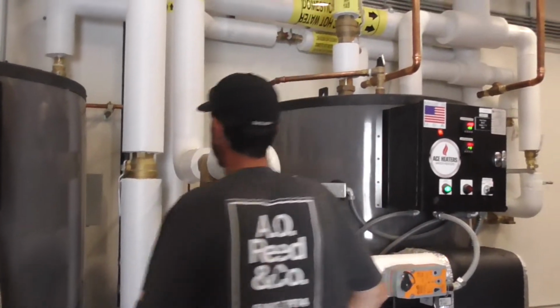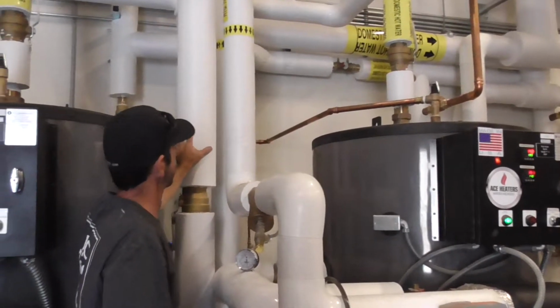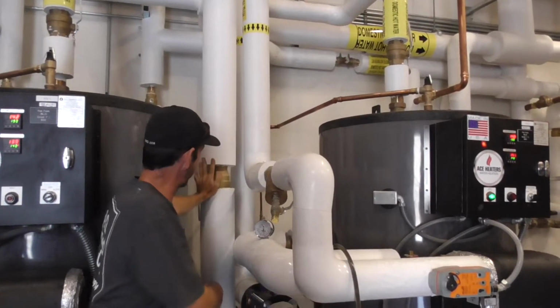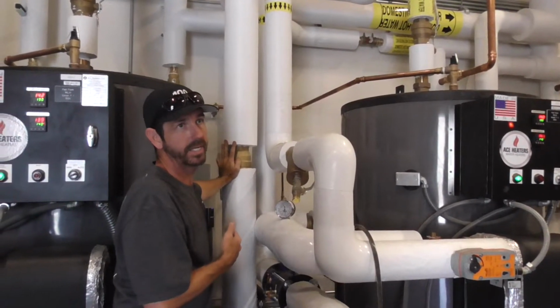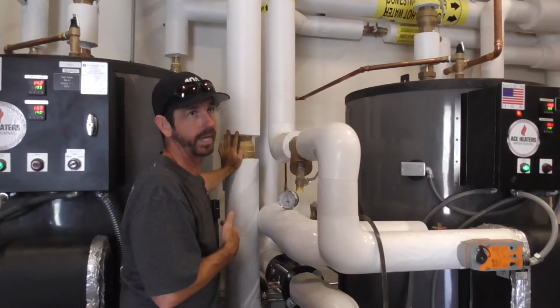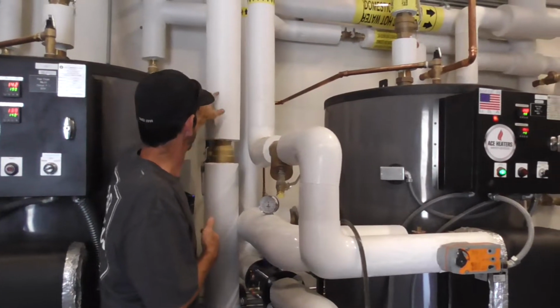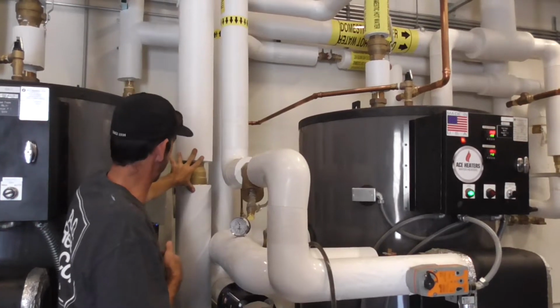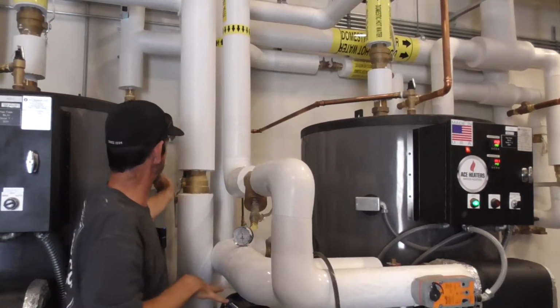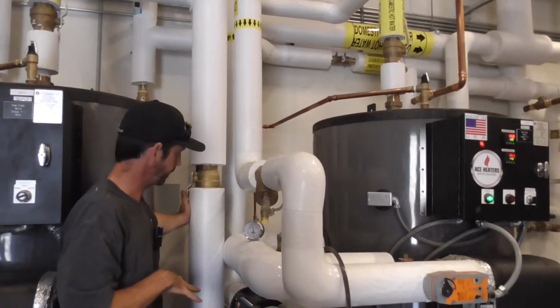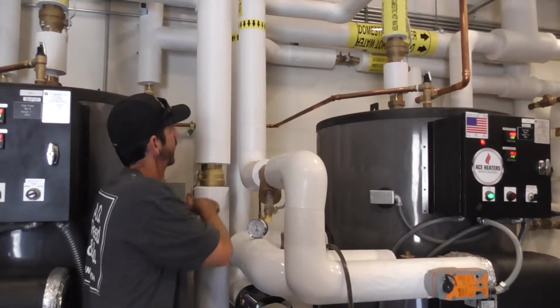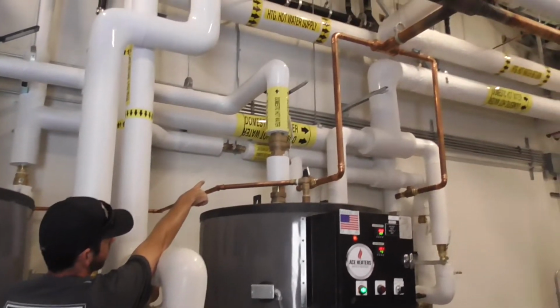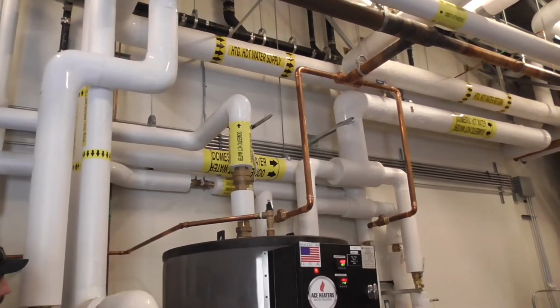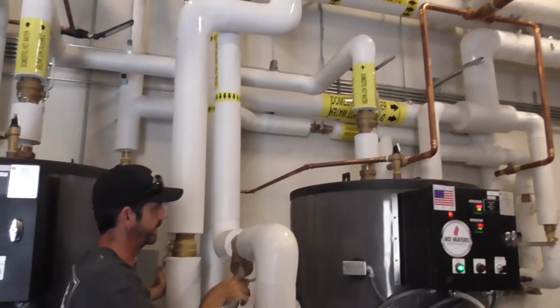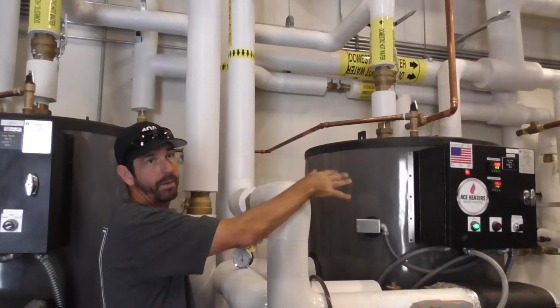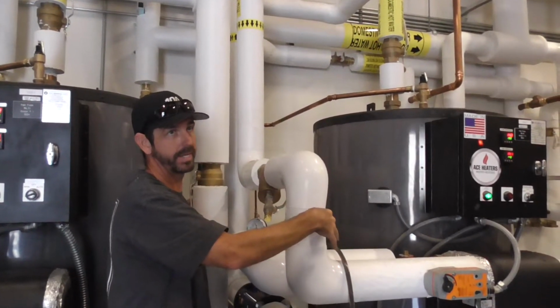So for the domestic side, right here, we have our domestic cold water in to the bottom of the tank. It's insulated because it is part of our return system, okay? Our domestic hot water return system. The domestic makeup is part of that right now. So if you needed to work on the unit, you can shut this valve right here. This would be your main cold shut, and then the main hot shut off is going to be the one up on the top, and that would isolate everything inside of it. If you did need to drain it, just make sure you turn off the unit, the power to the unit, because we do have a circulating pump inside as well. Okay.